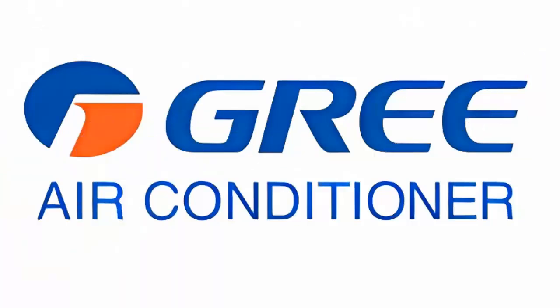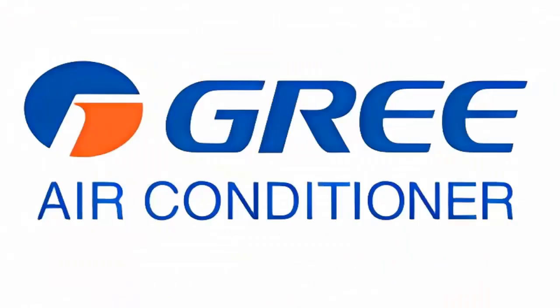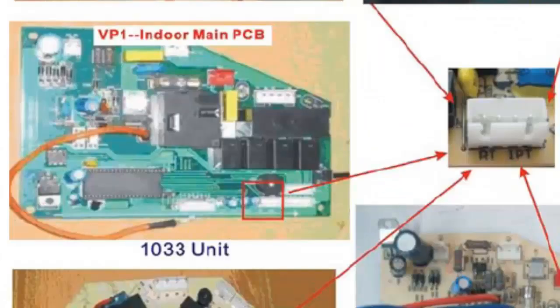7. If you have the unit's manual, compare the measured value with the sensor's characteristic table. Otherwise, replace the sensor. 8. If the error persists, visually inspect the electronic board that controls the sensor for faults. Consider replacing the involved electronic board if the problem continues.